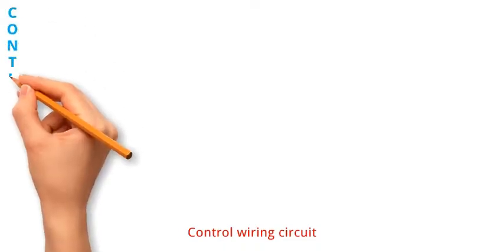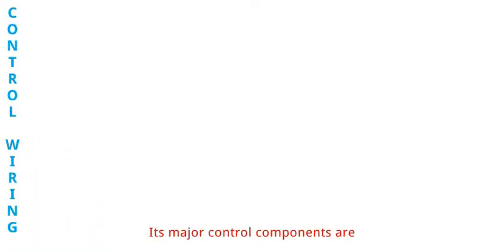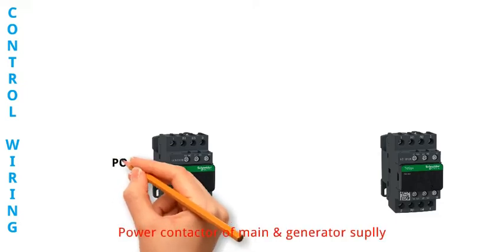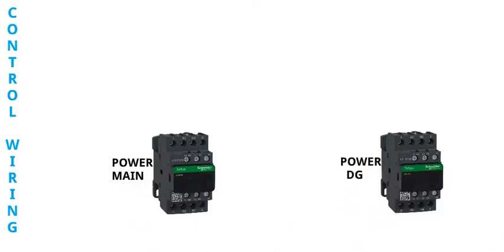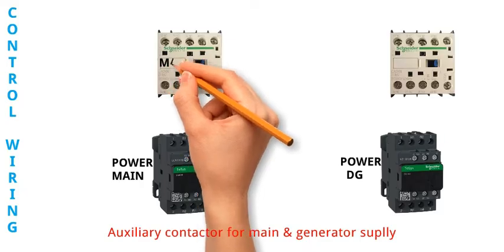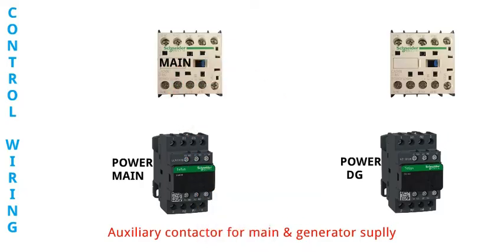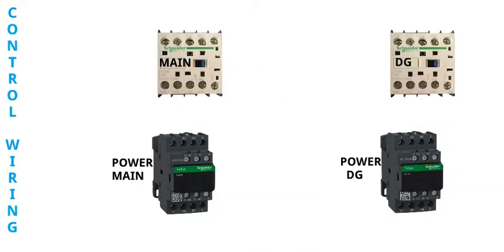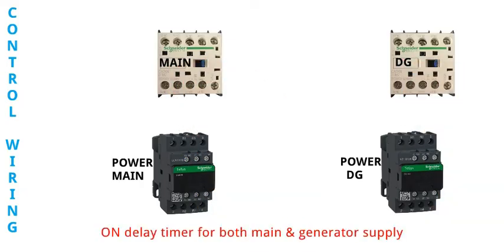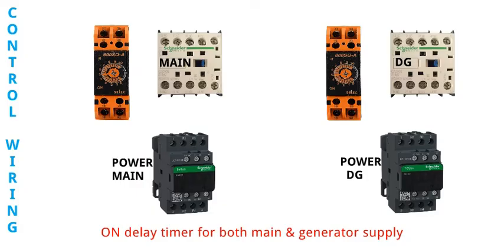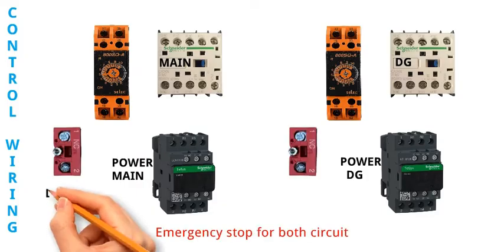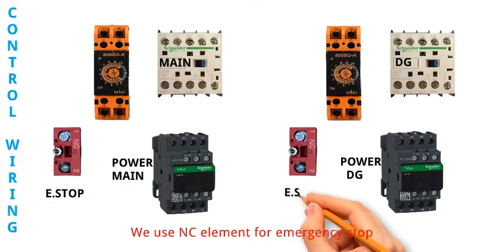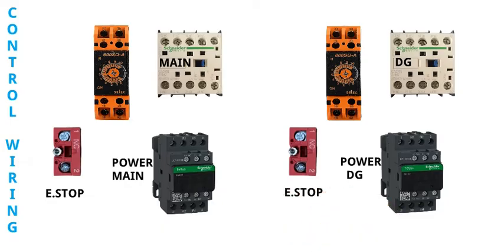Control wiring circuit. Its major control components are: power contactor of main and generator supply, auxiliary contactor for main and generator supply, on-delay timer for both main and generator supply, and emergency stop for both circuits. We use NC element for emergency stop.